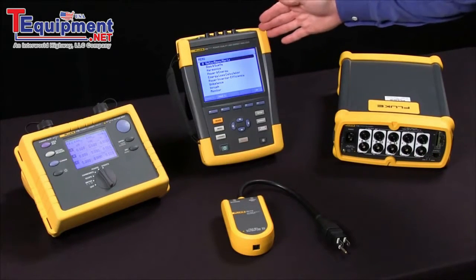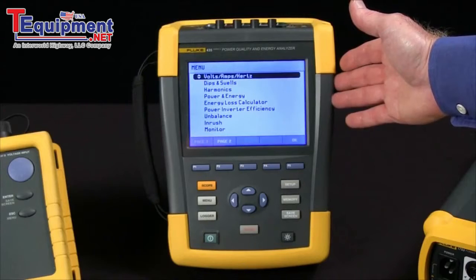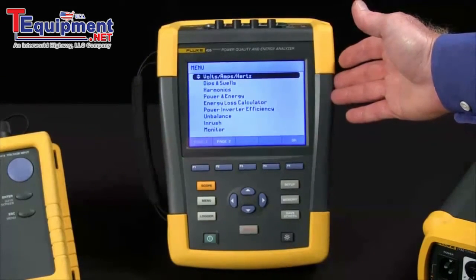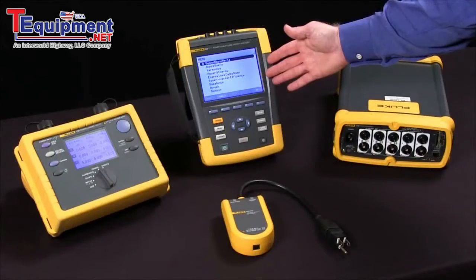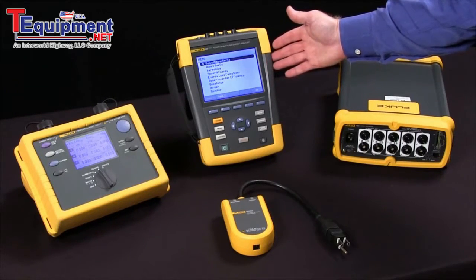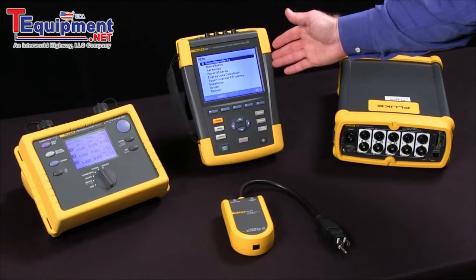The Fluke 435 is more of a troubleshooter. We've got a nice big screen that allows you to see what's happening in real time. It's got eight megabytes worth of memory as compared to the 1735 with only four megabytes, and it's got 200 kilohertz sampling, which allows us to capture transient events we would have missed with the Fluke 1735.